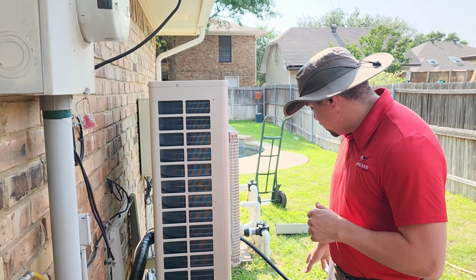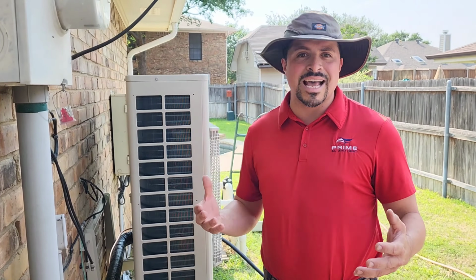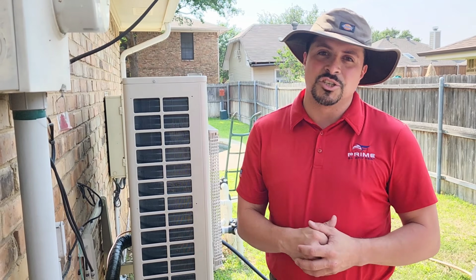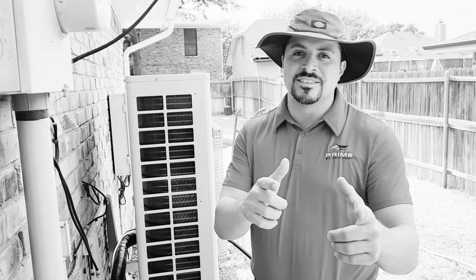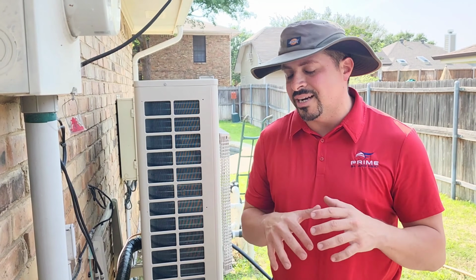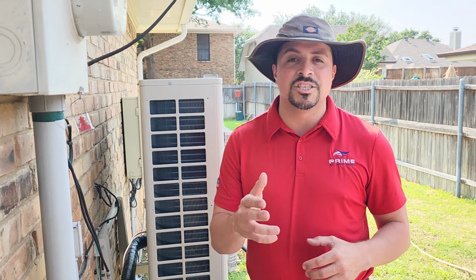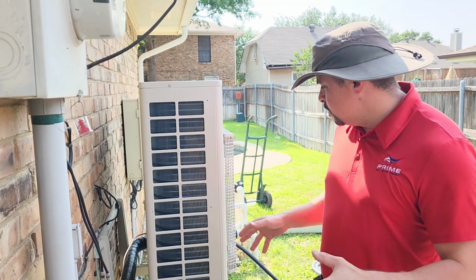Our guys also have the unit in a vacuum, and if you've seen our last videos, you know where we're trying to get to: 250 microns. That's going to ensure that all the moisture is out of that copper before we introduce the refrigerant. So couldn't be happier out here.